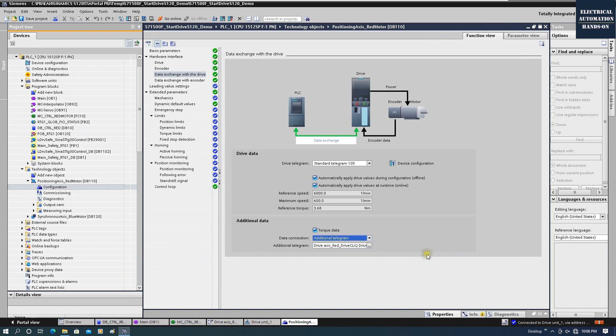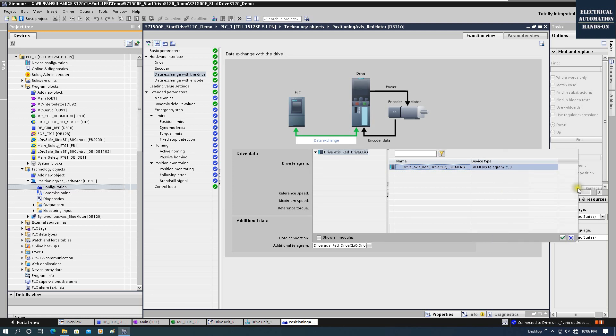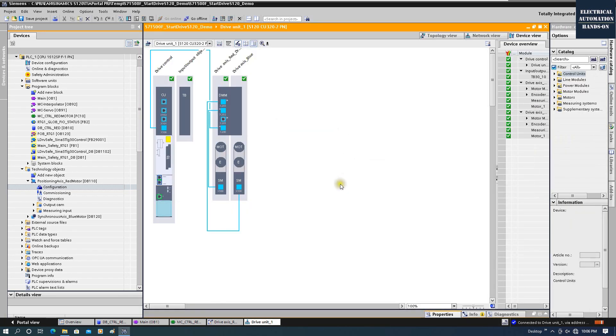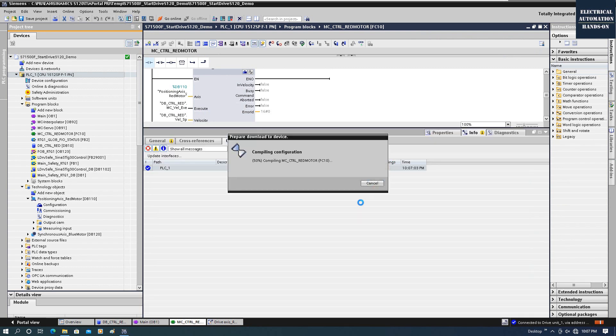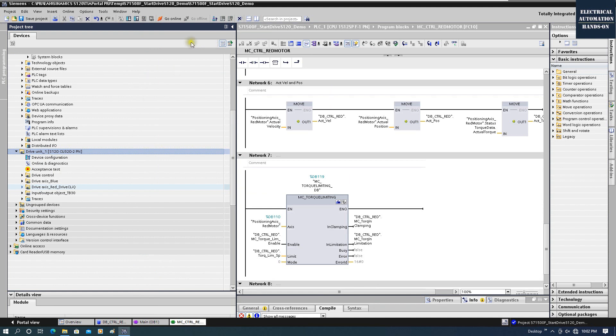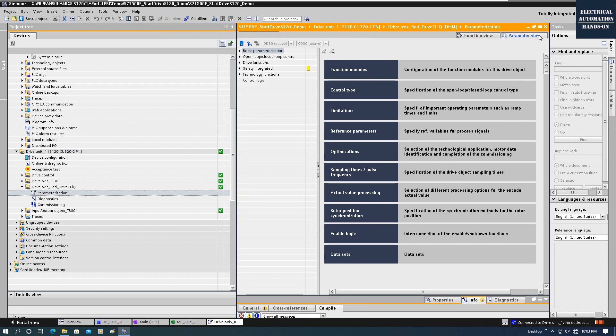Let's go to the TO torque data and make sure I select the red motor. After adding telegram 750, you will see the selection. Now we are ready to download to the PLC and drive. When downloading, the PLC needs to restart because we enabled telegram 750 and need to download the hardware configuration — the CPU needs to restart. Then we can download the S120 servo drive and go online.